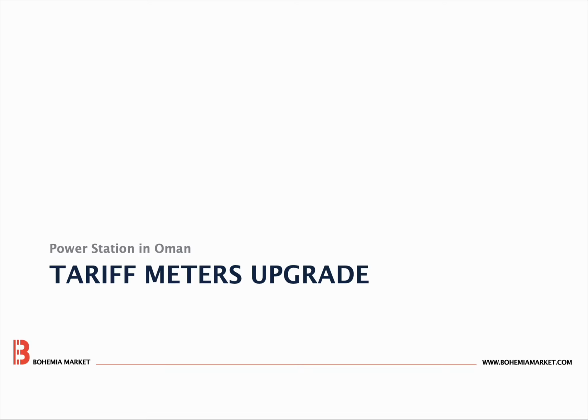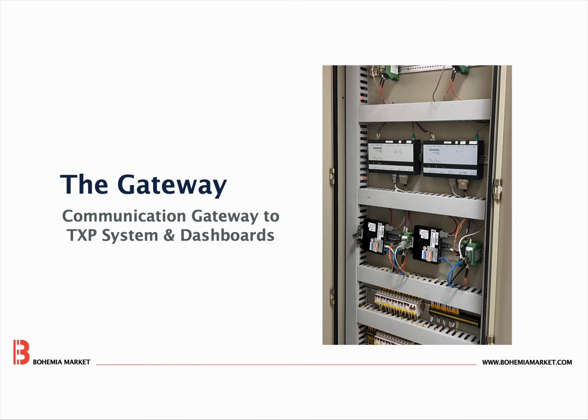Replacing tariff meters introduces a new challenge. Modern meters use different protocols, different addressing, and different communication methods. They do not match what existing control systems were originally designed to accept. Direct integration would require changes to the DCS or SCADA systems, which is usually not acceptable. On this picture, we can see the communication gateway to the TXP system.